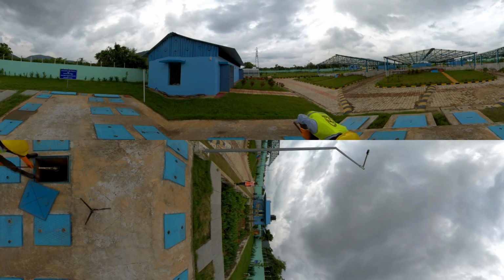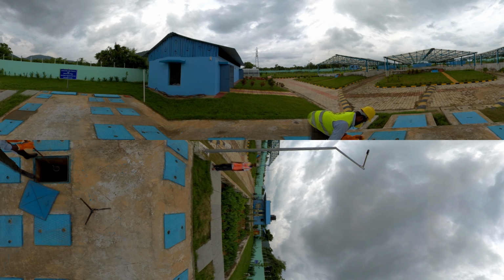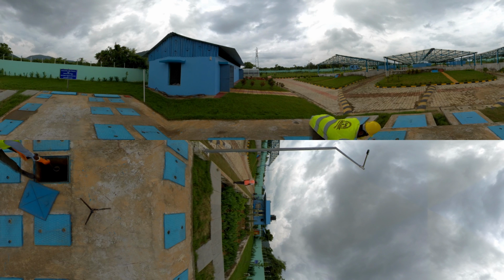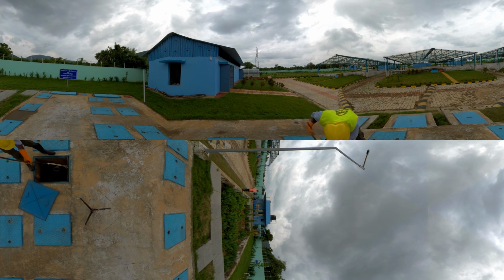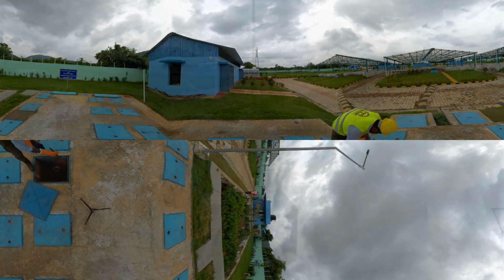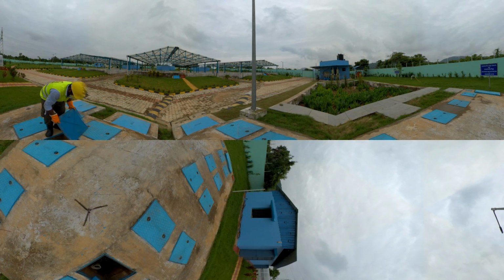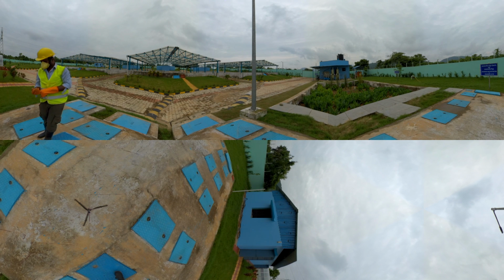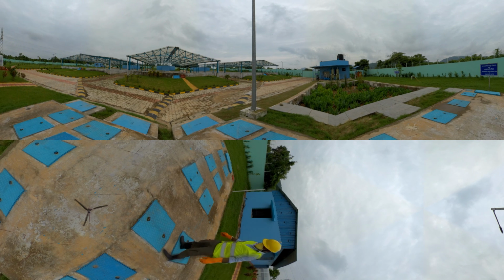Operation 1. Every 15 days, you have to open the inspection hole covers at every inlet and outlet to ensure that there is no obstruction in pipes. If there is no flow or if it is slow, use a steel wire and a long steel sieve to remove any floating solids or deposits. Remember to cover the inspection hole after completing the activity. Flush the water by opening the outlet of the inspection chamber. If the pipes are of short length, please use the L brush for cleaning.